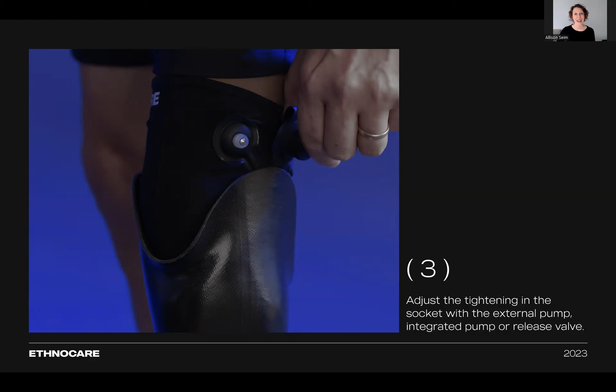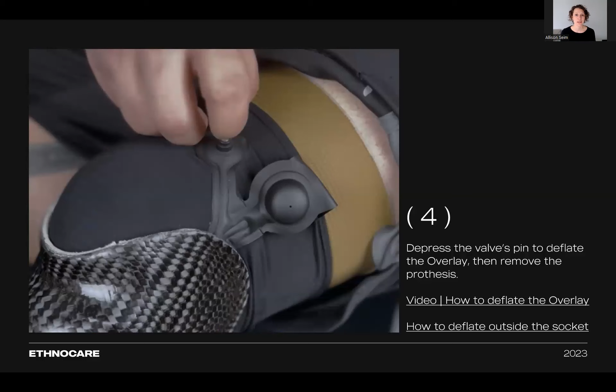During the day, when the user experiences any change in limb volume, they simply need to use the product's integrated pump to add air into the system without removing their clothes or their prosthetic device. To deflate the overlay, the user can press on the silver button situated on the release valve before removing their prosthetic device. It's easier to deflate when there's counter pressure from the socket on the air expansion system. Think of this similar to an air mattress.